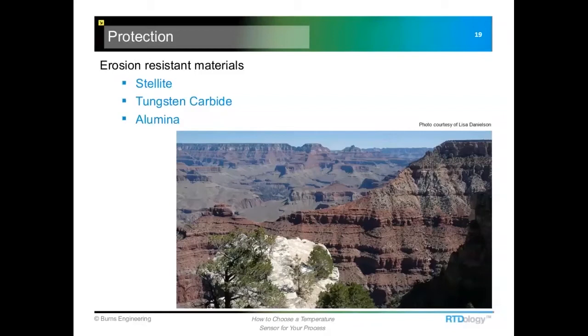We had an interesting case a while back where a company that makes the grit or the gravel that goes on asphalt shingles, part of the process is they're blowing this through a pipeline, and it goes past a thermowell that has a thermocouple in it. They pulled the thermowell out and the probe because they were getting some intermittent temperature readings, and they found that about half of the thermowell and most of the thermocouple had been completely sandblasted away. What was surprising is that as the thermocouple was being sandblasted, the two conductors in there actually kept touching each other, which is why they kept getting a temperature measurement, but about half of it was gone.